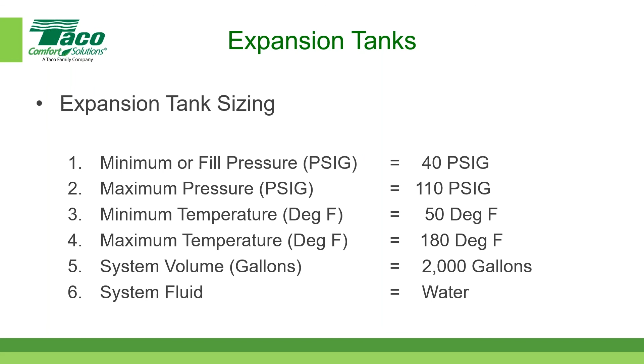Minimum temperature, maximum temperature - chilled water system, use 100 degrees. Minimum is what your fill temperature is - ground temperature, 40 degrees, 50 degrees, 60 degrees, depends where you are. And then the one everyone always says is the hardest one to get is system volume. We have some software that can help you get that. There may be some quick methods other folks may suggest you use, maybe even some of our reps do, but nonetheless you do need the system volume. And then system fluid - you need that information as well.